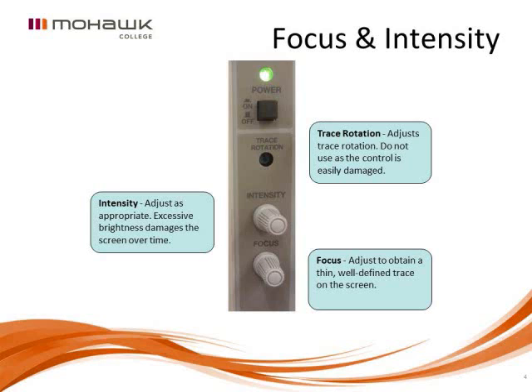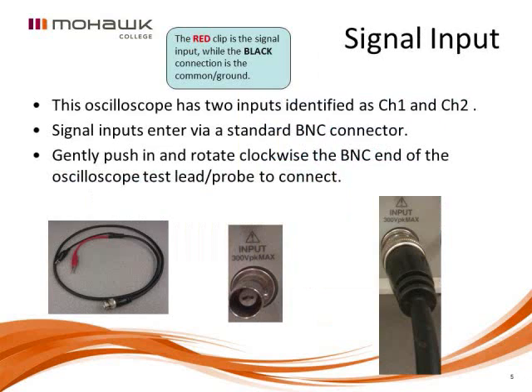The focus and intensity controls are used simply to set the sharpness and brightness of the trace. The intensity is simply the brightness — you don't want to set it too bright and leave it that way over a period of time, because you can damage the coating on the inside of the screen. Set it to a moderate setting — not too dim, but not excessively bright either.